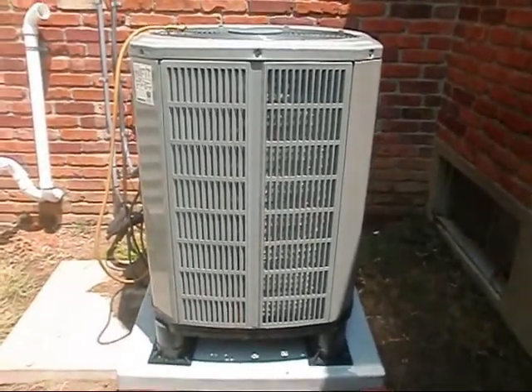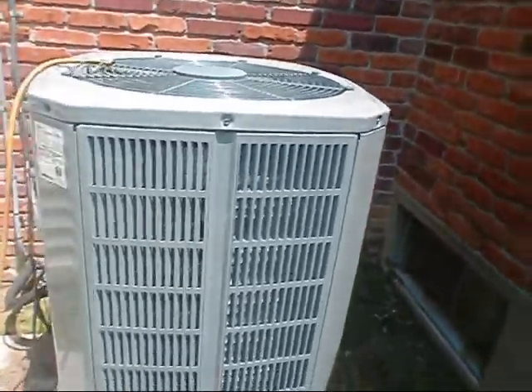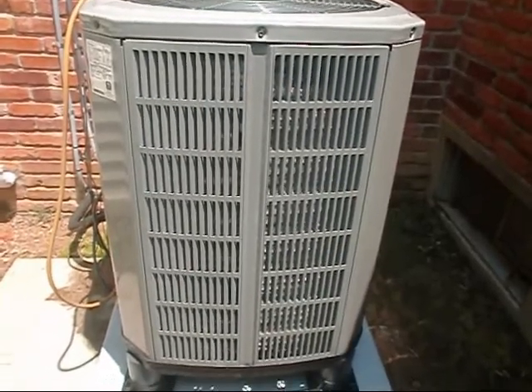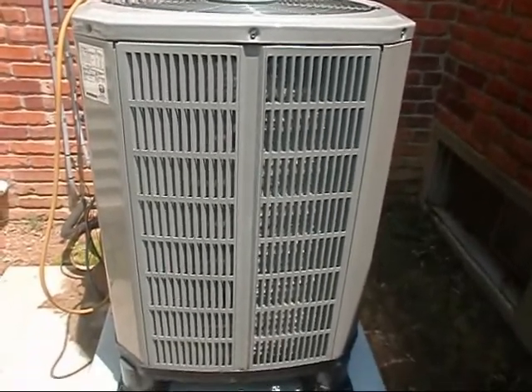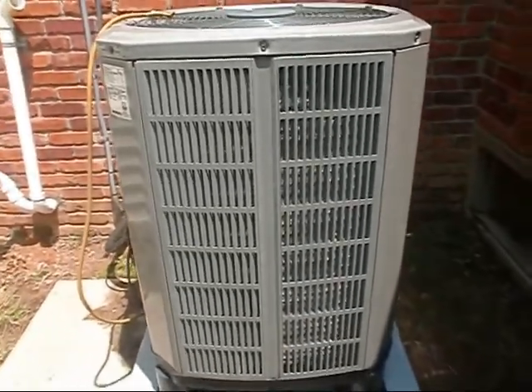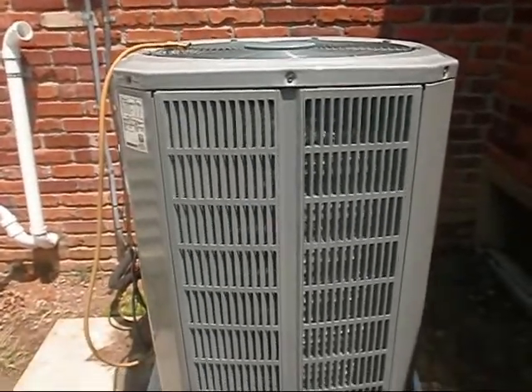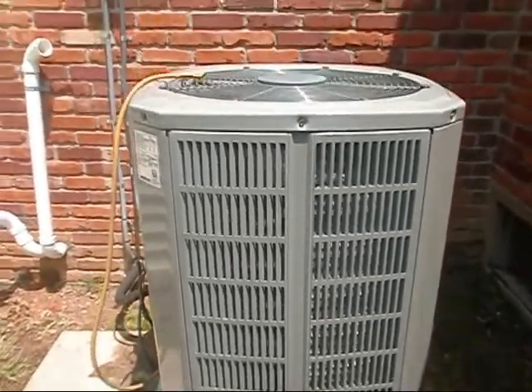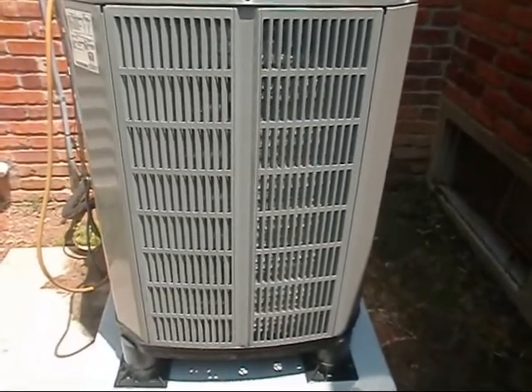She's been running for about 25, 30 minutes now — time enough for the ground to dry up. It's 94 in the shade, guys. It's hot and humid. We took the time to shine her up, washed her down with the coil cleaner real good, inside and out. We opened up the top and that thing was full of liquid. She's got a lot of trees back here and we've had some bad weather. We got all the drain hole openings in the bottom of that composite plastic pan open. We took the compressor motor at 11.7 rated load amps — I believe we were at 8, so we were well within the limit.